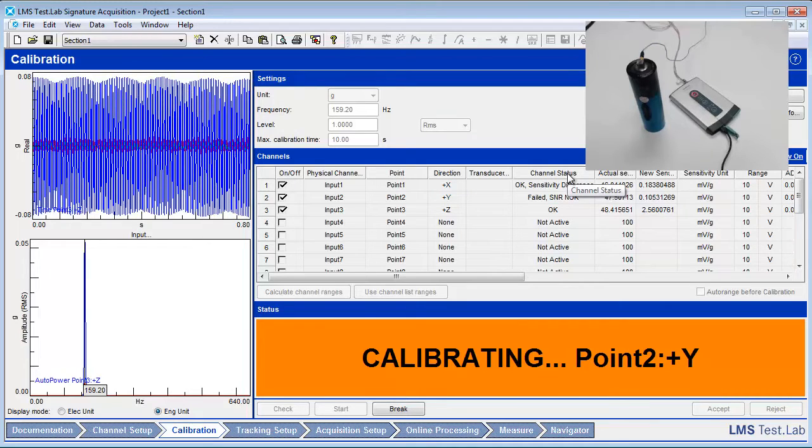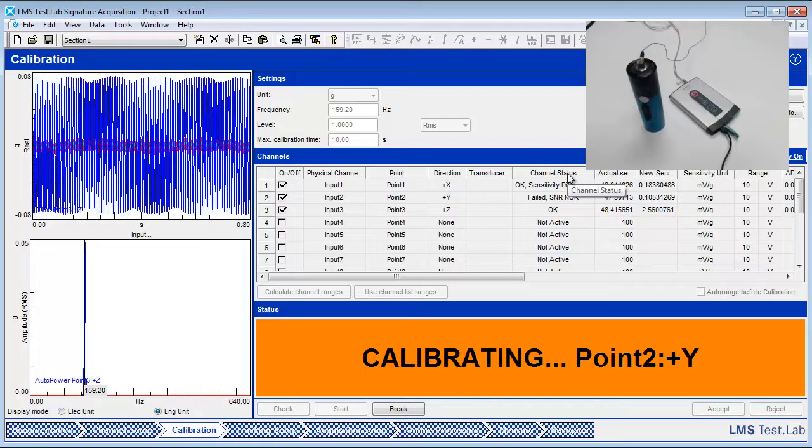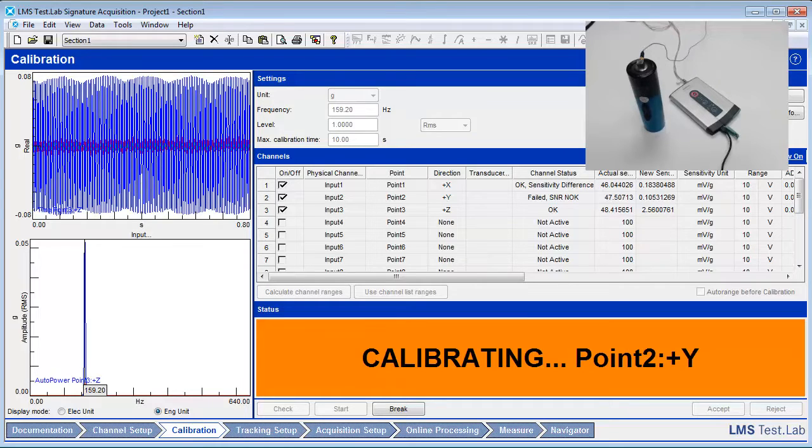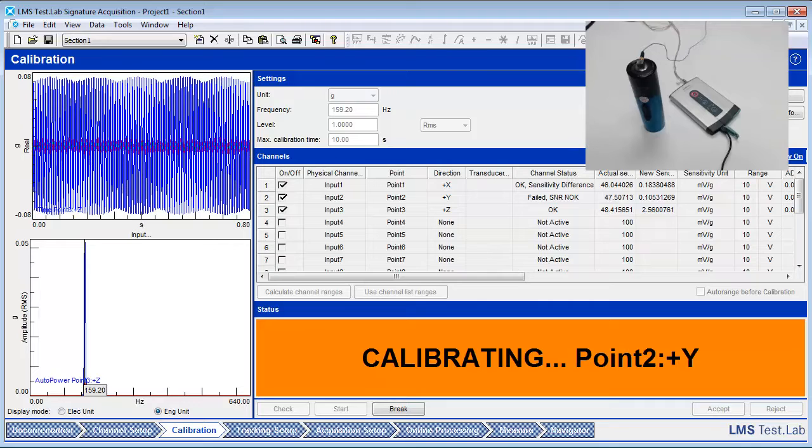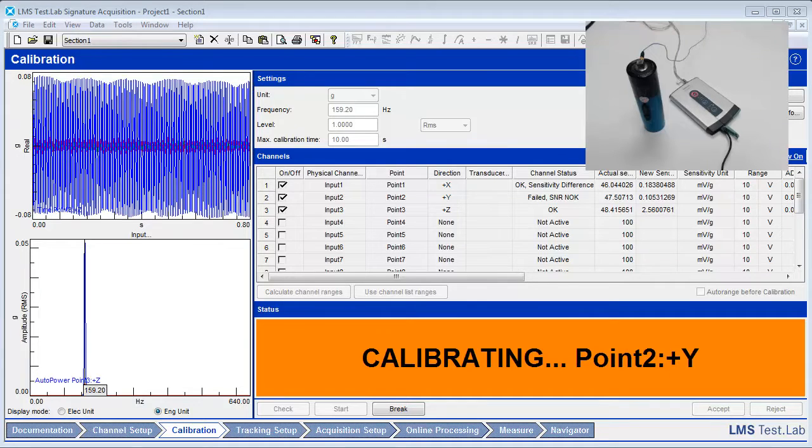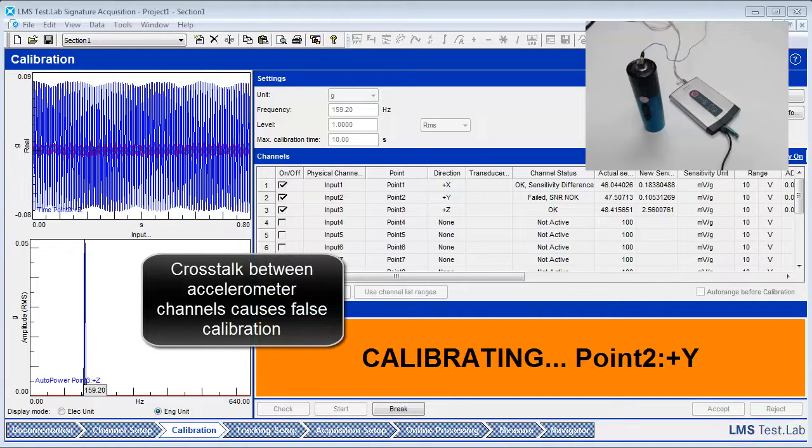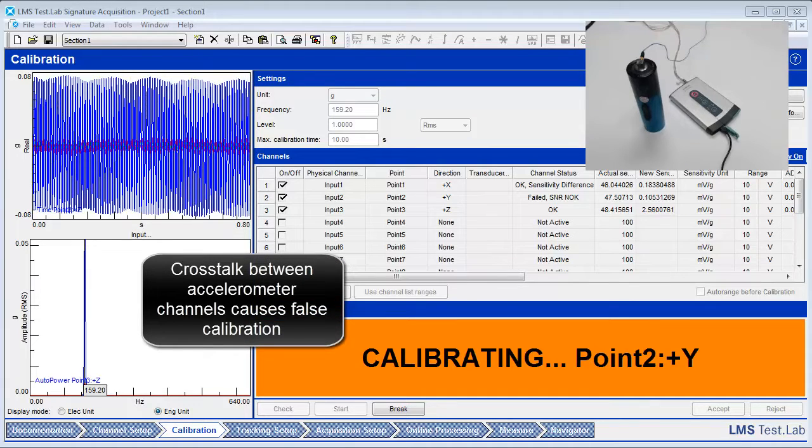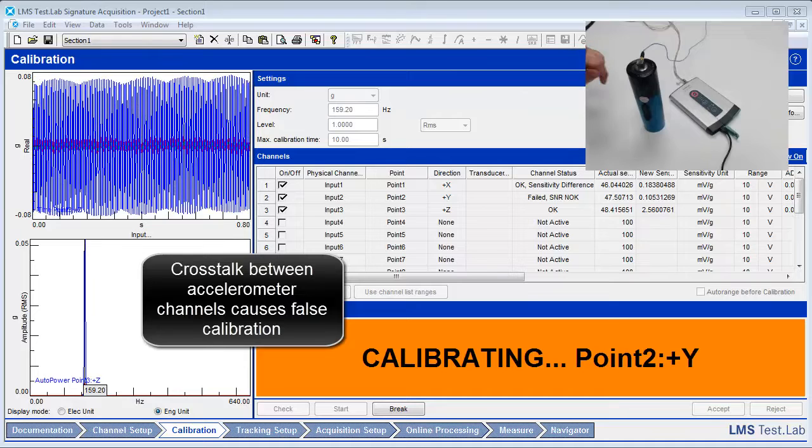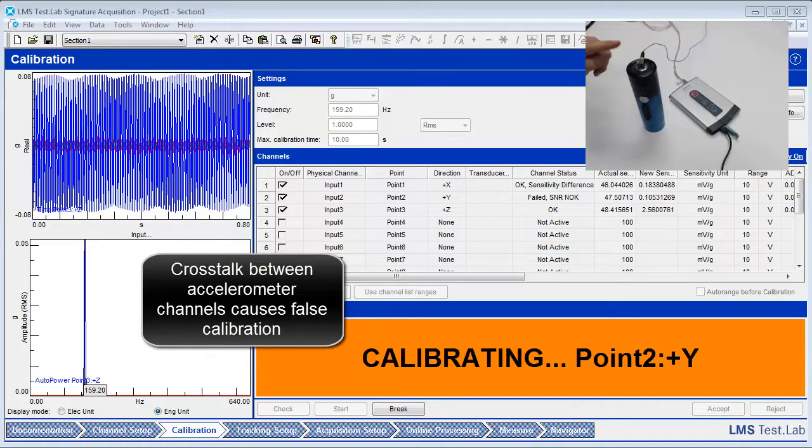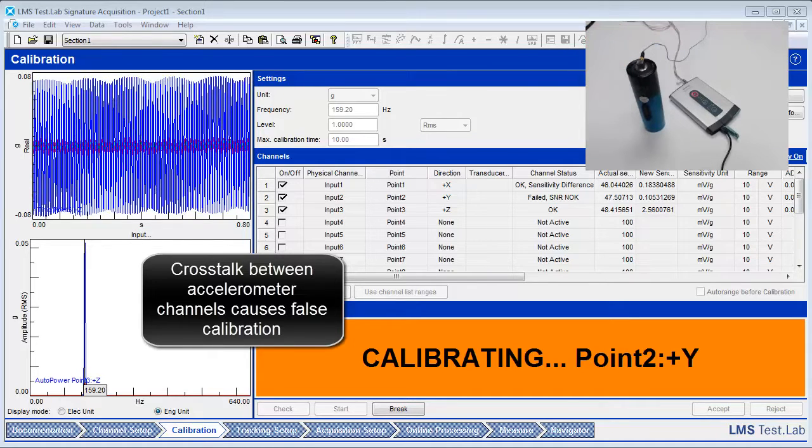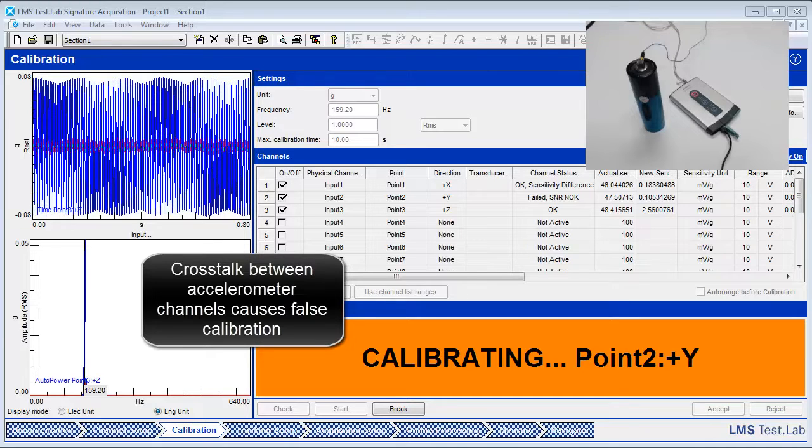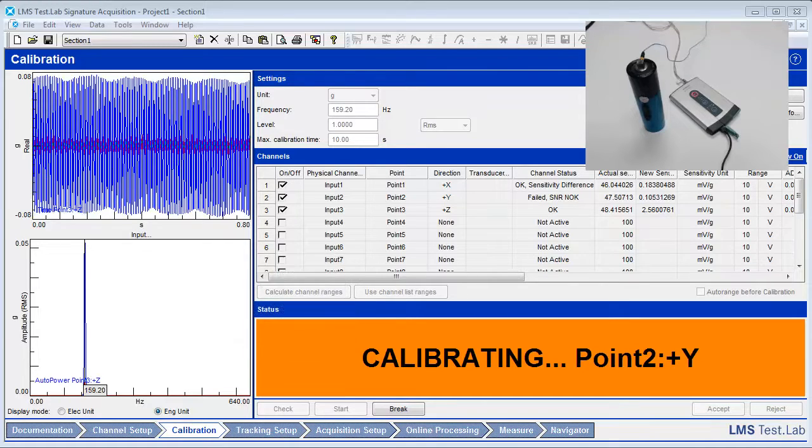Ideally, while one direction is being calibrated, the channel status of the two other directions should not have a calibration value calculated. If channels other than the intended direction of the accelerometer are being calibrated, cross-talk is occurring between channels within the accelerometer. Cross-talk is when the primary input is one direction and the other directions pick up minute vibrations from the calibration signal. The software sees a calibration signal and causes it to calculate an erroneous calibration on the other direction.